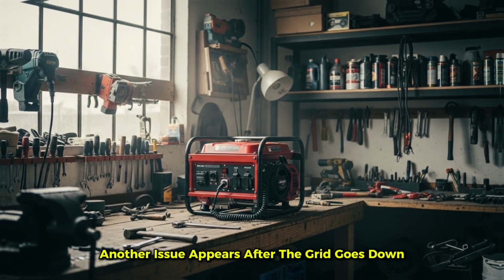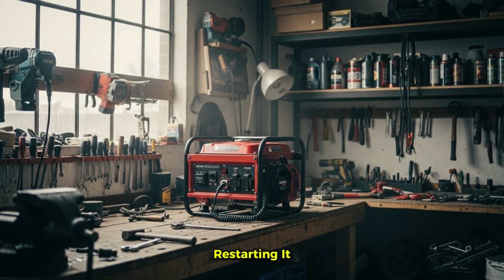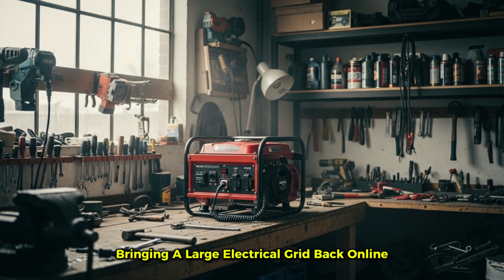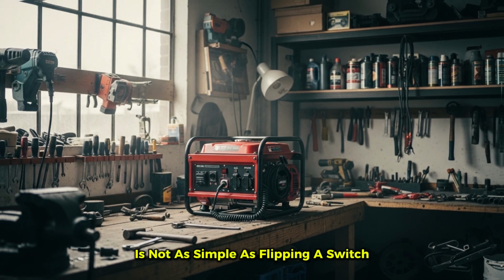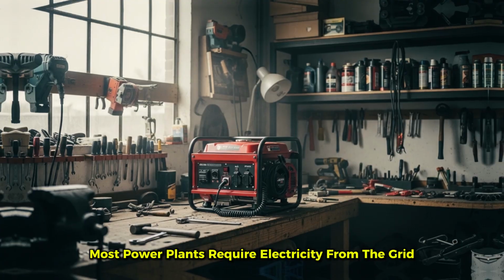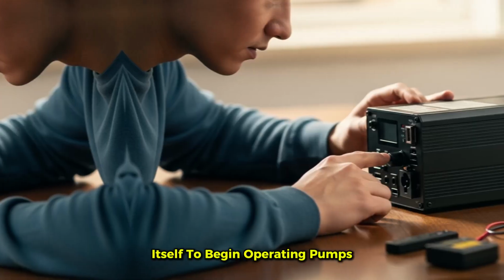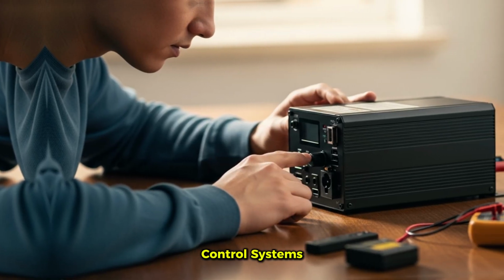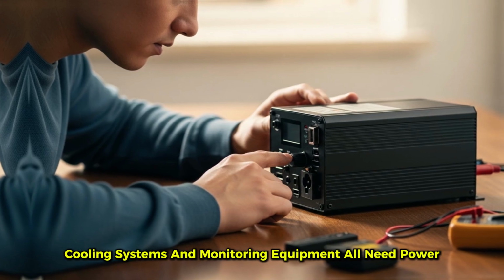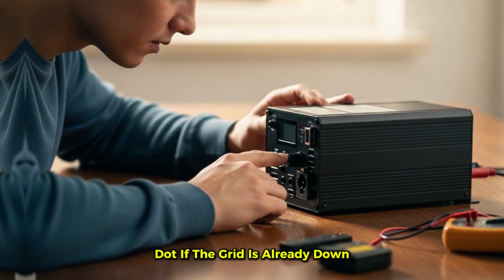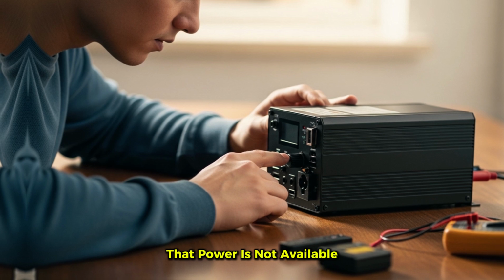Another issue appears after the grid goes down. Restarting it, bringing a large electrical grid back online, is not as simple as flipping a switch. Most power plants require electricity from the grid itself to begin operating. Pumps, control systems, cooling systems, and monitoring equipment all need power. If the grid is already down, that power is not available.